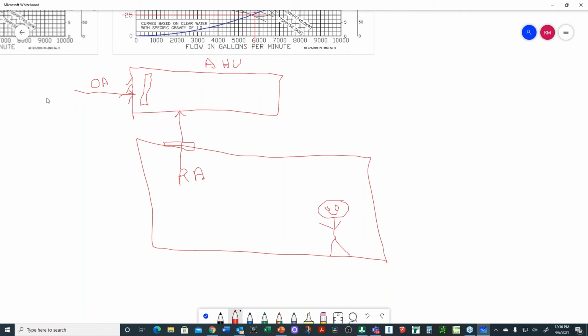And those two mix together. And let's say, again, we're talking about heating today. So let's assume that the outside air temperature was 5 degrees Fahrenheit. And then we have a filter. So I'll just put an F in here for filter. I'll put a filter right there. And then these two air streams mix. The outside air mixes with the return air, and then it passes over a heating coil. Like I said before, we call that a heating coil. And then we'll have a fan in here, and it'll be the grossest fan you ever saw. Put an F for fan.